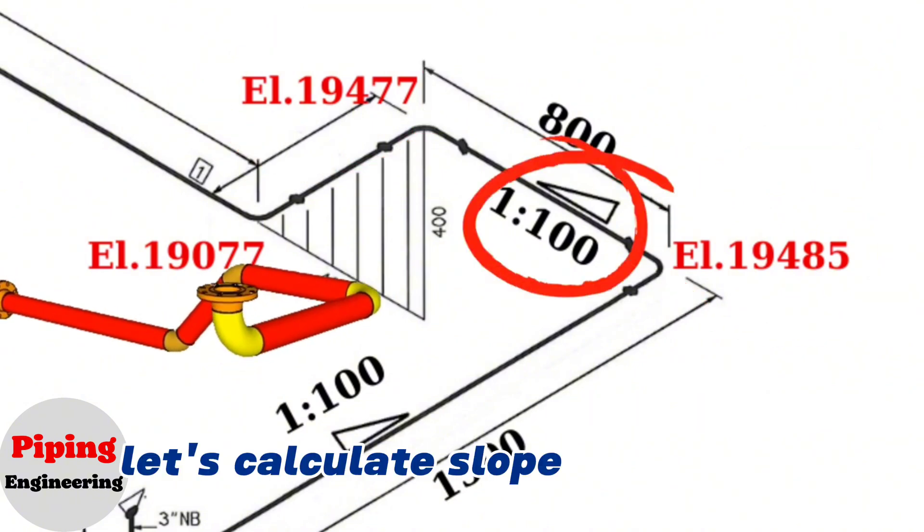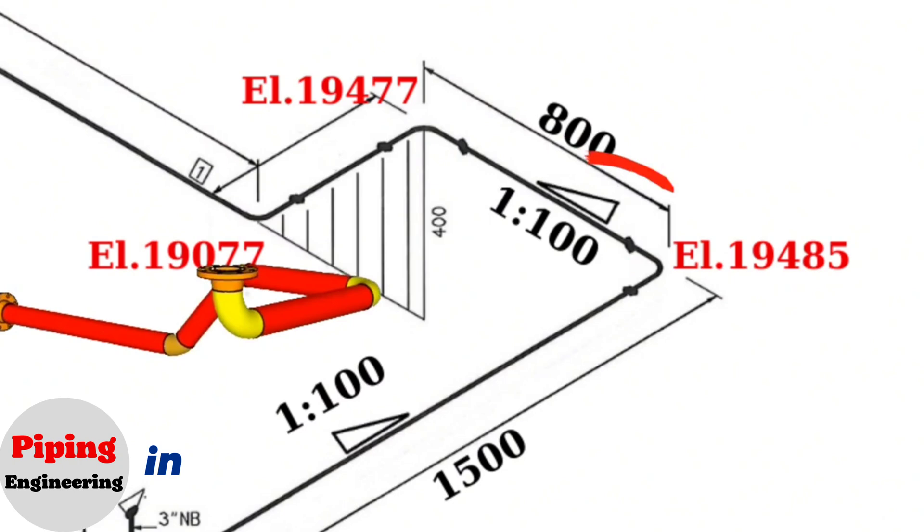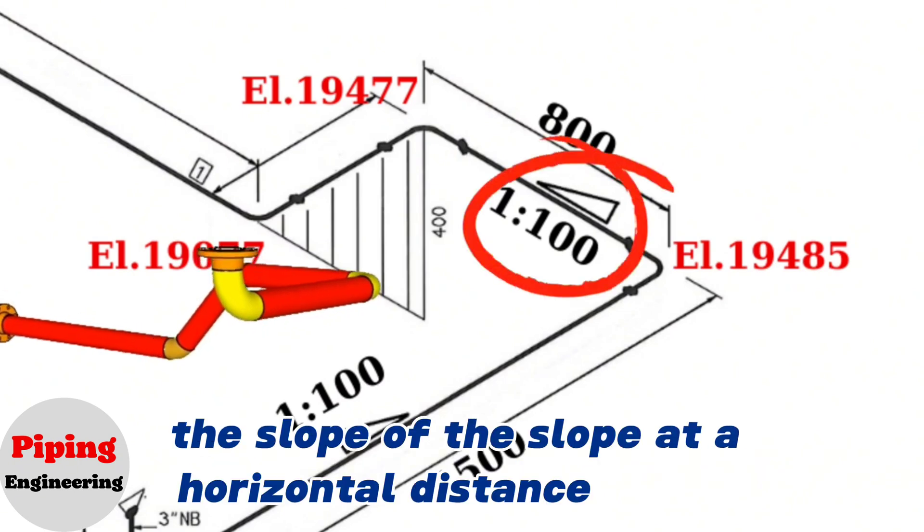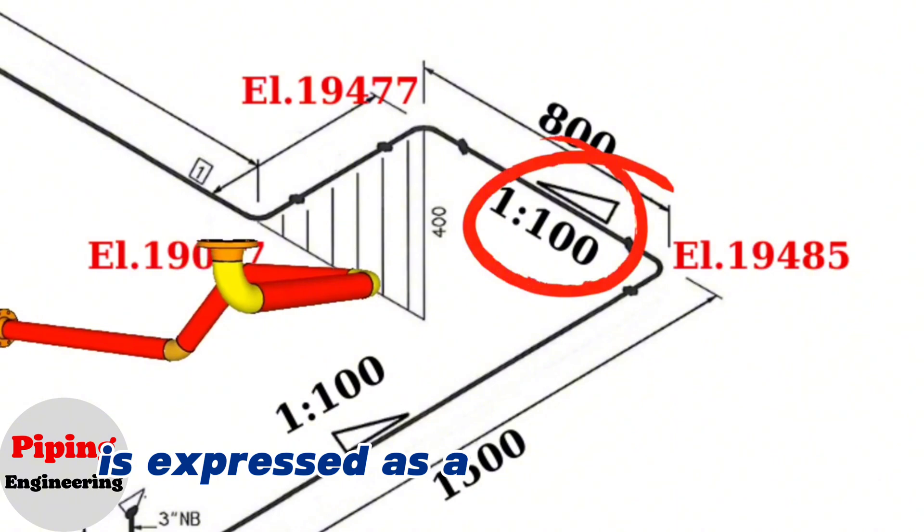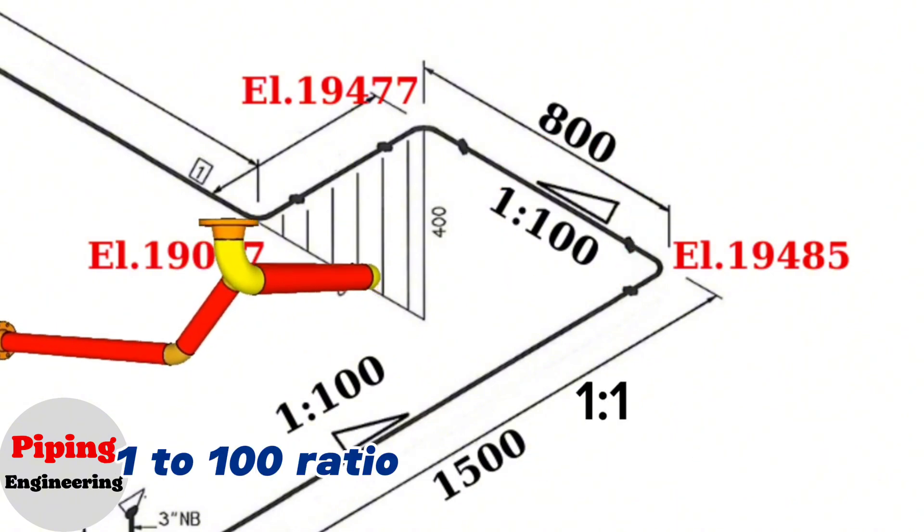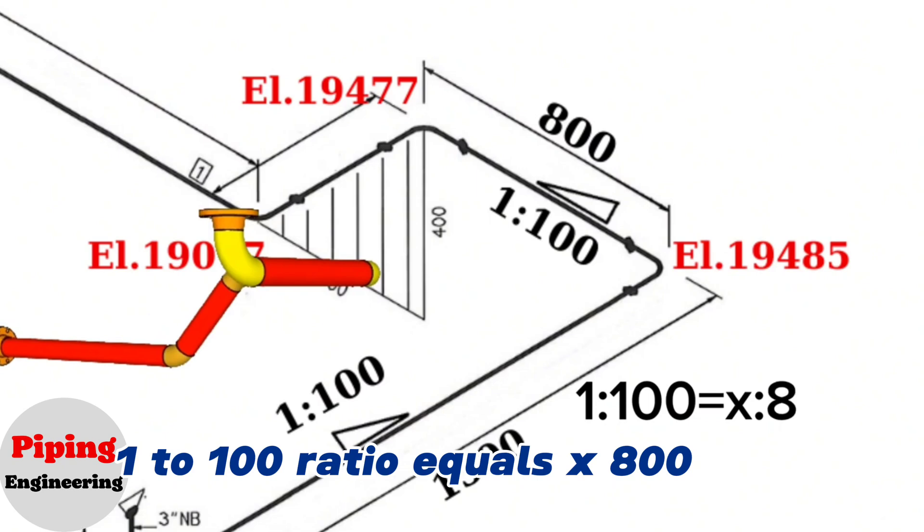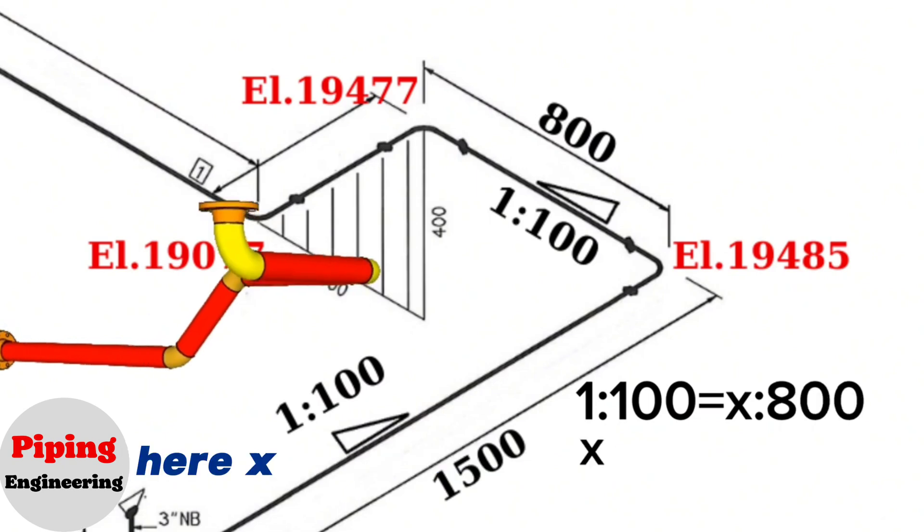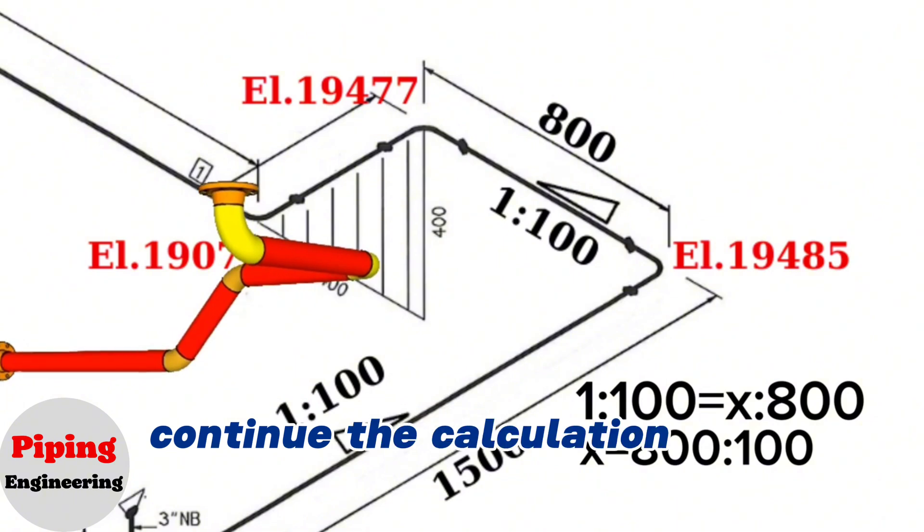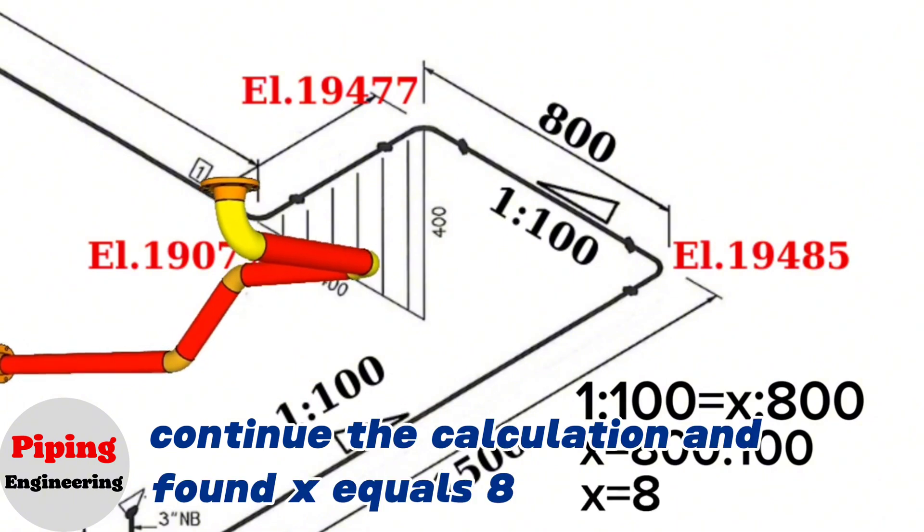Let's calculate slope ratio now. In this pipe isometric drawing, the slope at a horizontal distance of 800 is expressed as a ratio of 1 to 100. 1 to 100 ratio equals x to 800 ratio. Here x equals 800 to 100 ratio. Continue the calculation and found x equals 8 mm.